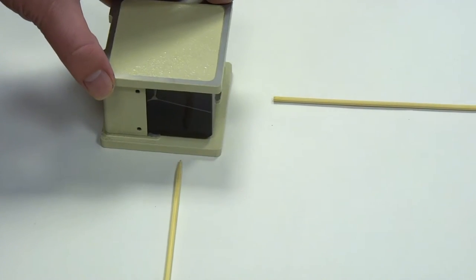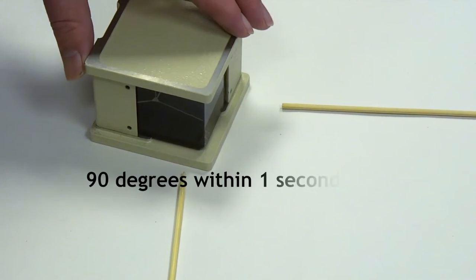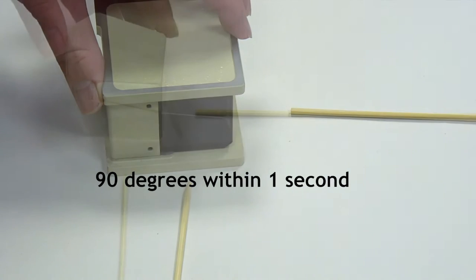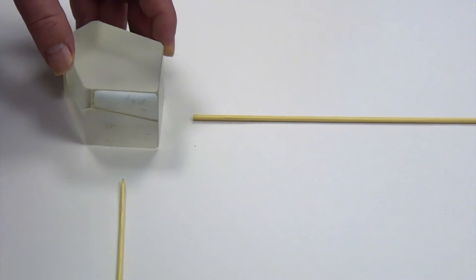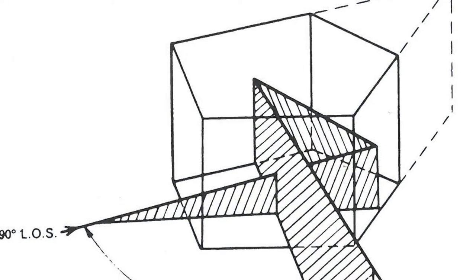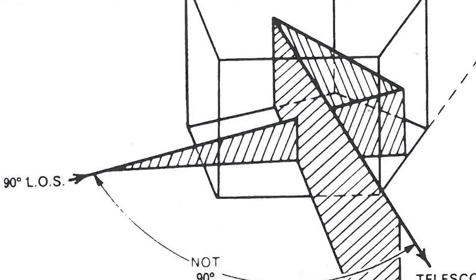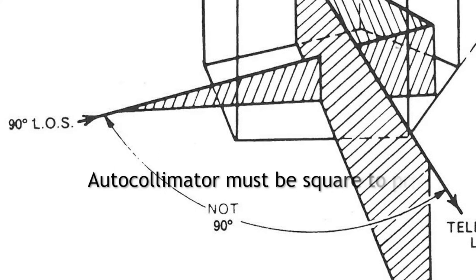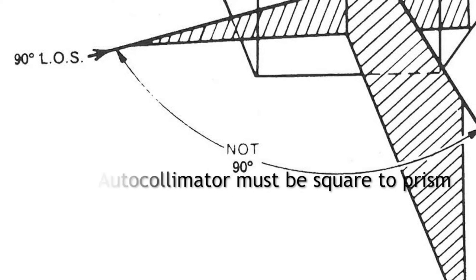As long as the front face of the pentagonal prism is square to the autocollimator, the line of sight or beam will be bent by 90 degrees. If things are not lined up square, i.e. the prism face is tilted forward, we can get an error in the 90 degree.